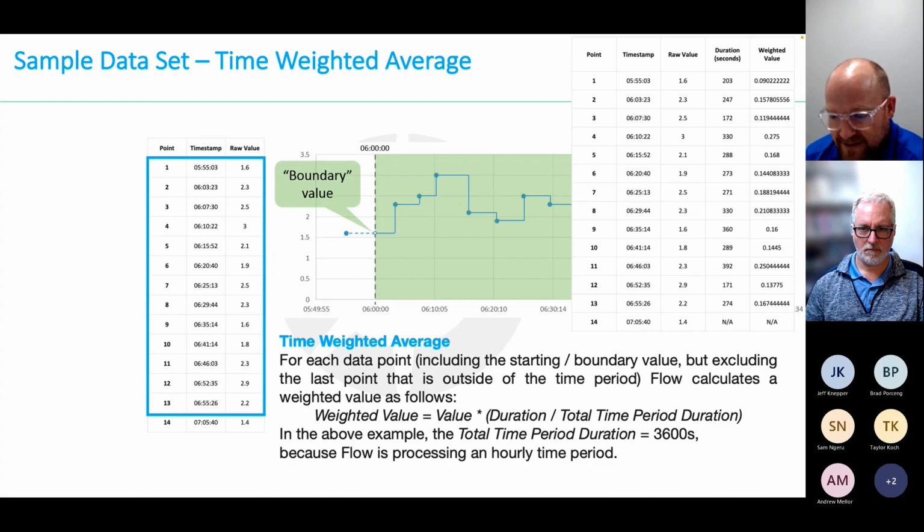Interesting little side fact, if you do cyclic retrieval or cyclic storage on data, so if you tell me I want to record a value every 5 seconds rather than delta (delta is what we like in the industrial world), time-weighted average and a statistical average will give you the exact same answer because the difference in time is exactly the same.